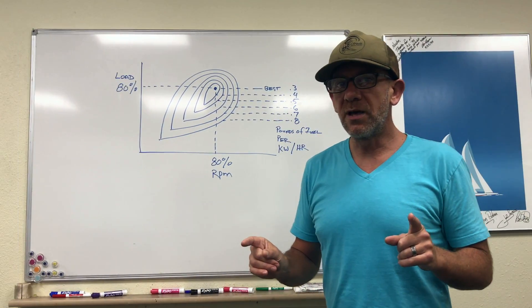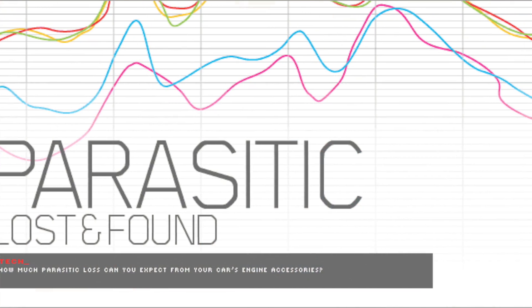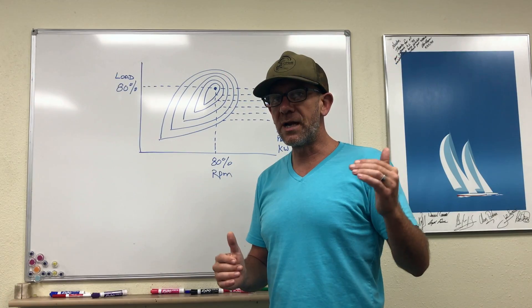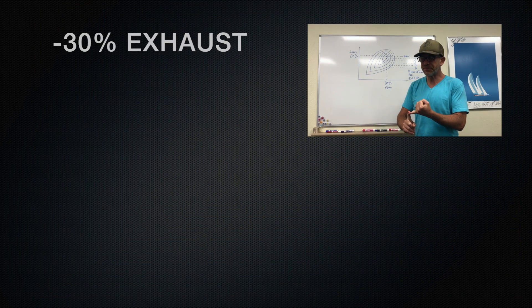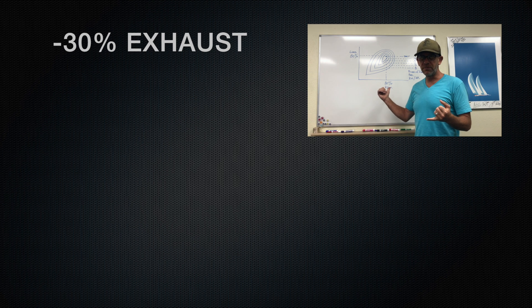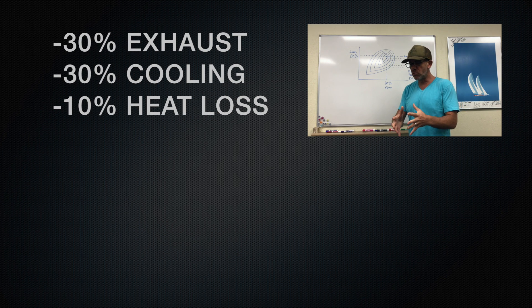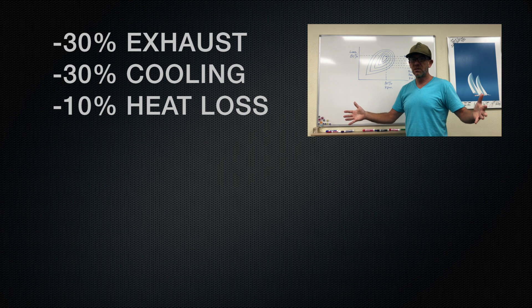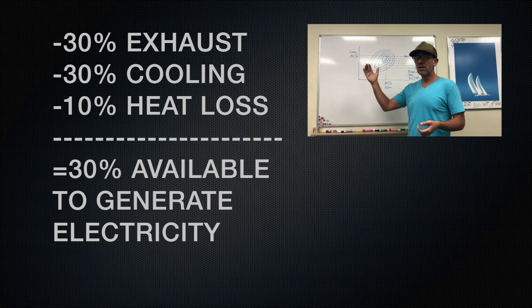Now when you run that fuel through a diesel motor, diesel motors have considerable parasitic losses. Those parasitic losses will detract from the overall power. So you're going to spend roughly 30% of the energy going out the exhaust pipe, another 30% is going to go through the cooling system, and then you're going to lose another about 10% of just radiated heat coming off of the block. So what you're left with is 30% of the available energy in that 130,000 BTUs that's available to generate electricity.